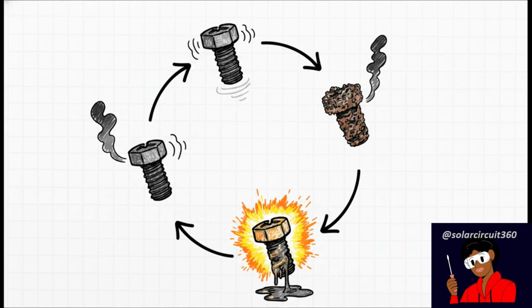It starts with that slightly loose bolt, which immediately causes increased contact resistance. And remembering our physics equation from earlier, that resistance instantly creates localized heating right at the terminal. That heat then causes the metal components to oxidize. And here's where it goes completely off the rails. The oxidation increases the contact resistance even further, which, of course, leads to an exponential heat rise. It becomes a self-reinforcing failure cycle. A bolt that just felt firm on day one will eventually melt your terminal entirely. It proves that even the most slightly loose connection is going to create a destructive, system-ending hotspot.